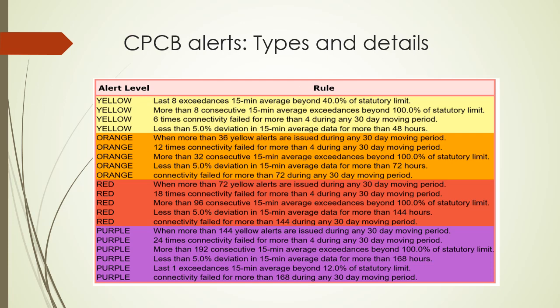If we go through each of them, we can prepare a prevention plan where we can keep the highest limit. For example, we can have the detailing of all the alerts, and we develop our own plan proactively. As I have spoken earlier in the earlier slide, there is a possibility that we can get the alerts as per our requirement from the vendor. For example, COD is 50. If I say give me an internal alert from the vendor side, that if my COD reaches 40, I should be notified, and the STP operator should be notified, and the STP manager should be notified.